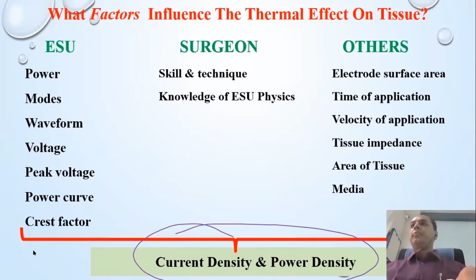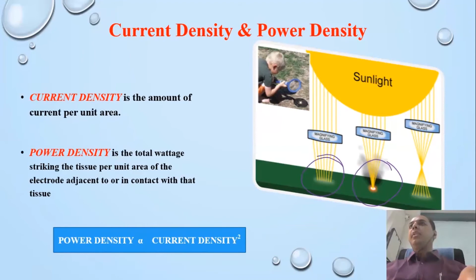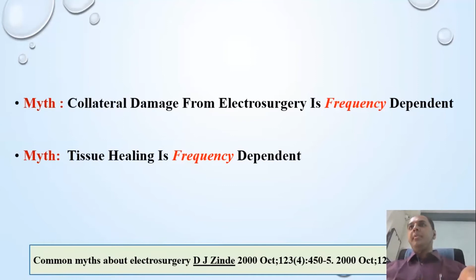Very high current density concentrated at the tip of an electrode can be used to heat and vaporize cells. Slightly lower current density may desiccate and coagulate, while the same current spread over a large area may have no impact on the cells, like in the case of using a dispersive electrode. So again, it is a myth that tissue effect or healing is dependent on the frequency at which an ESU operates.